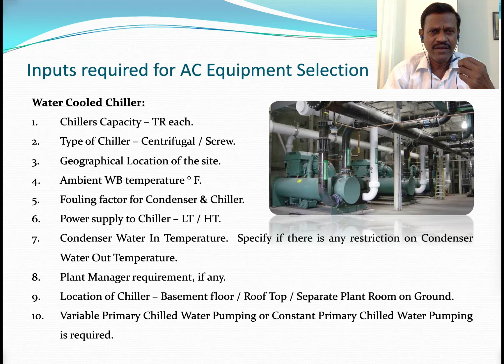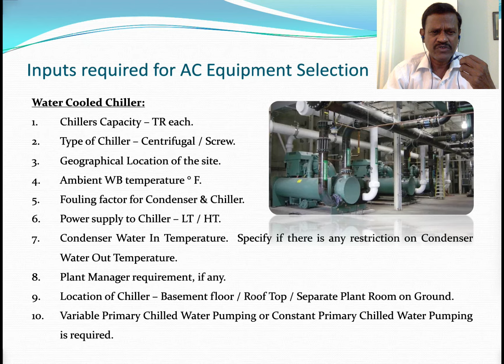Next, you have to specify whether a plant manager is required or not, and in the plant manager, what equipment you are planning to control through it. Next, say whether you plan to install the chiller in the basement floor, on the rooftop, or in a dedicated plant room adjacent to the building. Another important thing is to specify whether you want variable primary chilled water pumping or constant chilled water pumping, so that they select the chiller accordingly. These are all the inputs you have to specify to the vendor for the water cooled chiller.